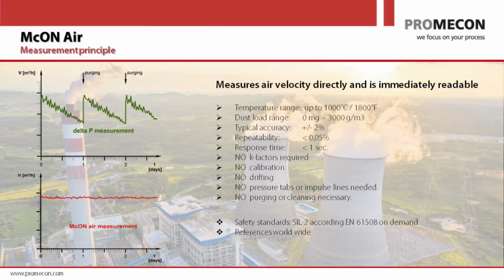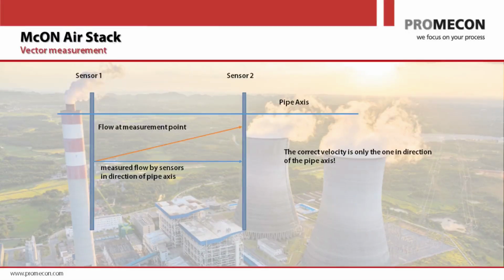If the gas velocity goes down, the time shift gets bigger because the gas needs a longer time from sensor 1 to sensor 2. So the more you go down, the larger the time gets. And at velocity 0, the transit time is infinite. So there is no zero point that we can measure, and therefore there's also no zero correction that we have to do. The measurement principle is very simple, and the simplicity of it is basically the beautiful part. There are no complex things. There is no fancy purge system, no fancy cleaning systems, no fancy correction factors. This is all dead simple. It's a velocity, a cross-section, and a temperature and pressure correction, and that's all.